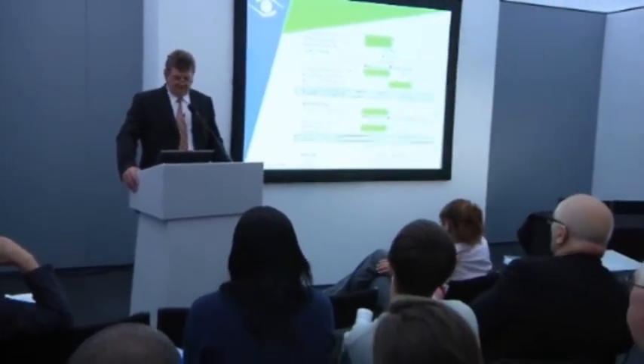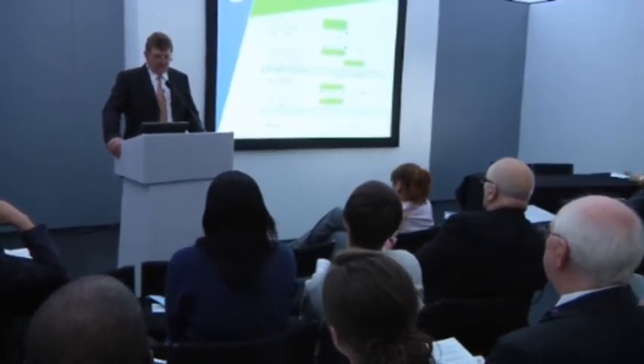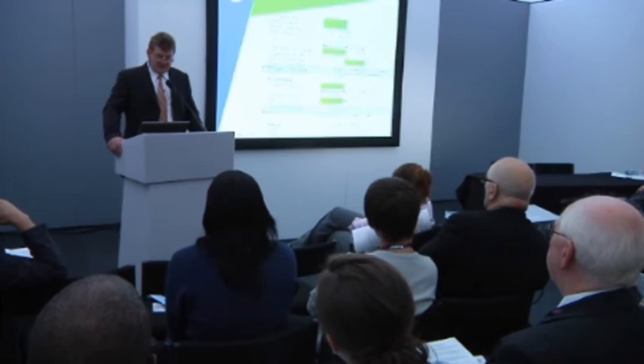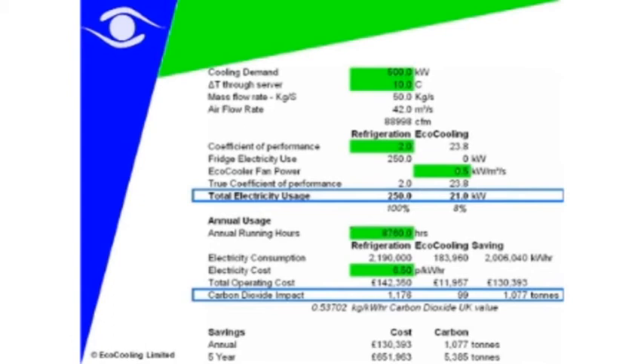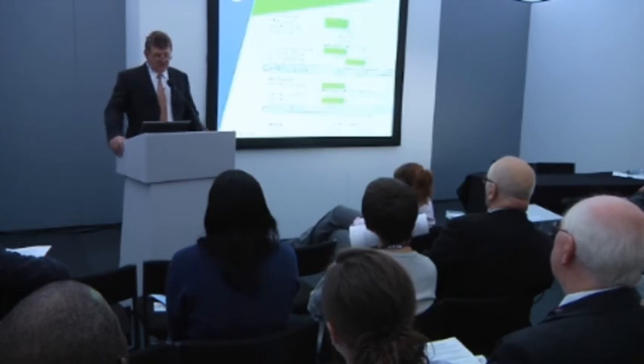What we're actually trying to do is give all the servers the right volume of air. Wherever that air comes from is irrelevant, but you've got to give it the right volume. 500 kilowatts of servers actually adds up to about 42 cubic meters per second of air — that's a lot of air. Looking at the comparative cost between refrigeration and an Eco Cooling CREC system: the coefficient of performance of refrigeration in a PUE 1.6 data center will be about 2, meaning for the 500 kilowatts of IT load we will be putting 250 kilowatts of energy continuously into the cooling system.